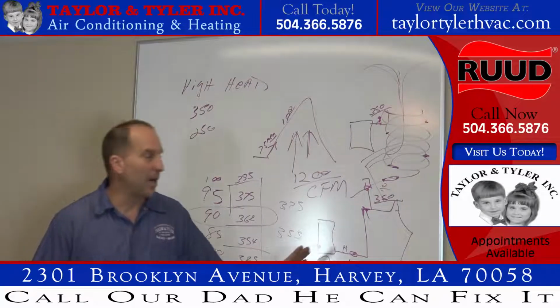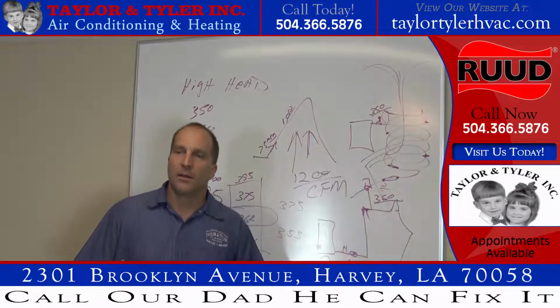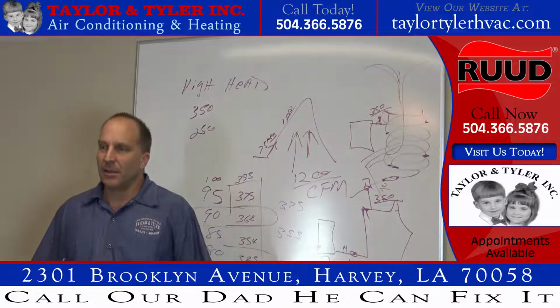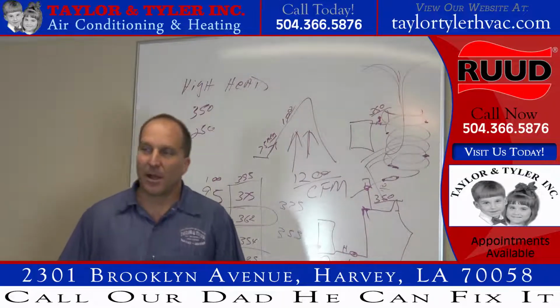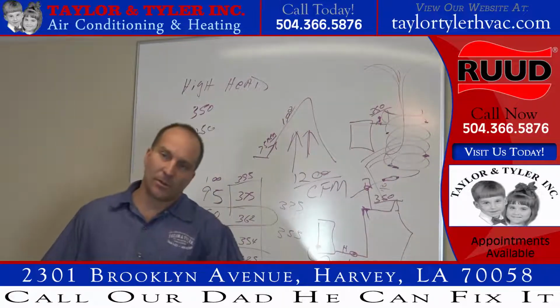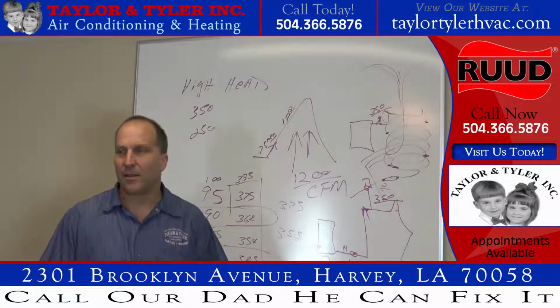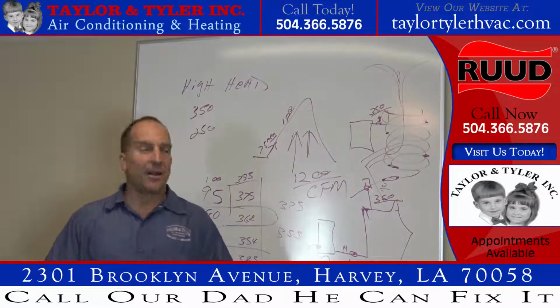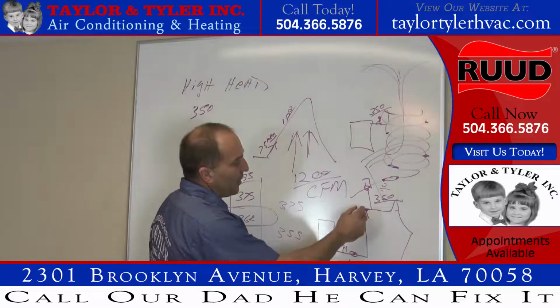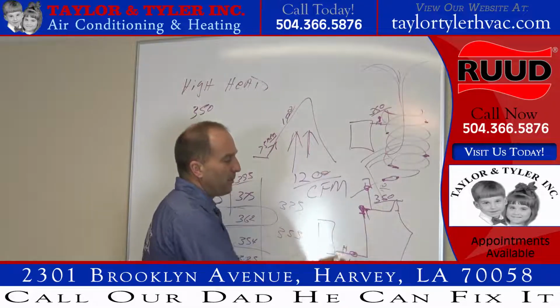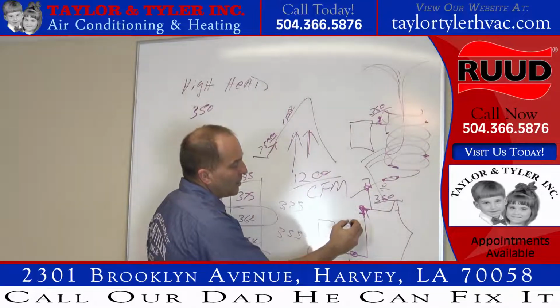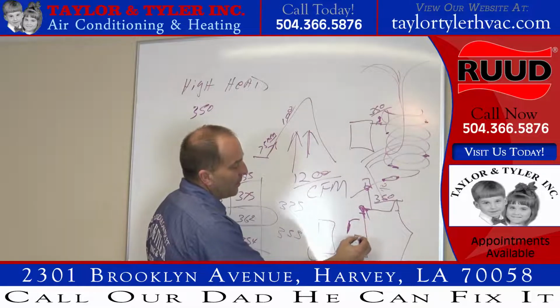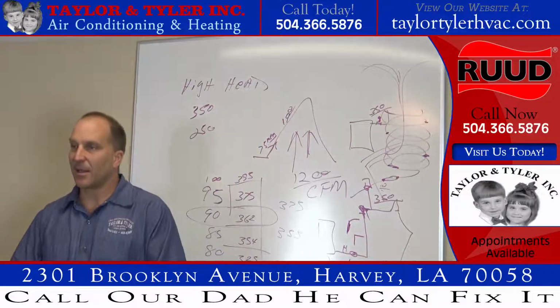The high side line was run through the wall, through the top plate, and somebody grabbed the line or they kicked it because they were doing something in the attic, and they pulled that high side line and it went through the top plate right here and it hit on that piece of metal and that line went like this, and it kinked the high side line.